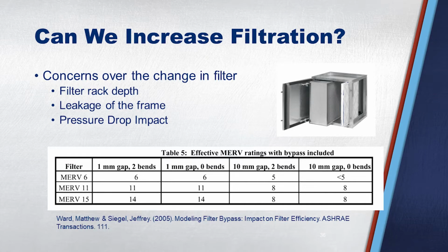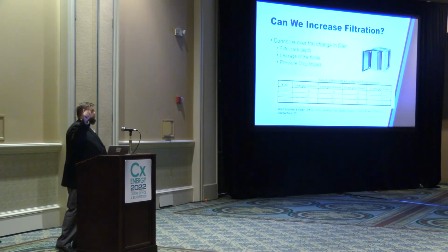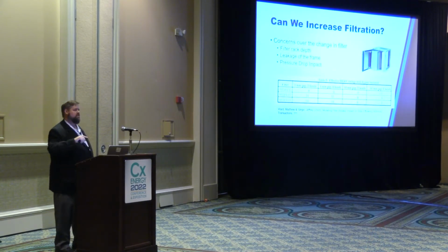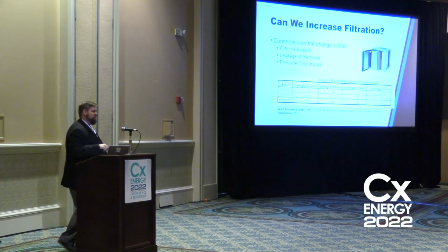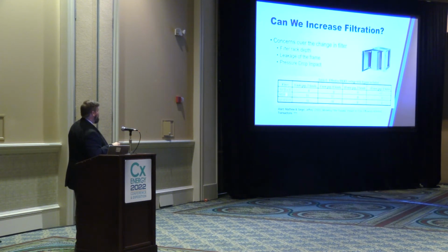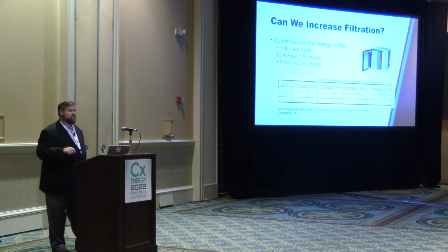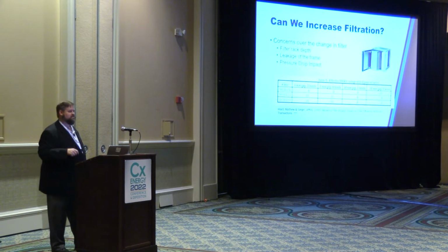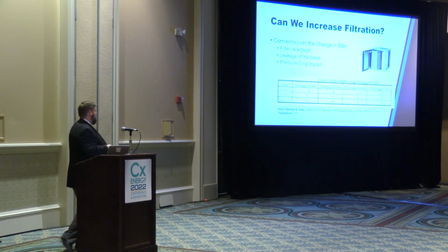It's this study done by Dr. Siegel. This was a modeling version they did. They've done 2 on-site testings of this that verify it, but the table's just not as nice, so I'm using that they align. But in essence, a MERV 15 filter with a 10 millimeter gap, less than a ½ inch, operates like a MERV 8. So how well my filters are installed is more important.